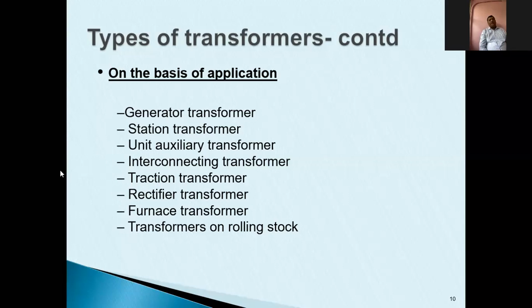When we are using rectifier transformers, in the case of HVDC substations, you will find the transformers are rectifier transformers. When you are coupling these transformers with rectifiers, there will be lots of harmonics. There will be lots of heat generated in this transformer due to harmonics. So we have to keep all these points into account. These harmonics, the higher frequencies, will affect my magnetic circuit. The eddy current losses will be more, the stray losses will be more. So I have to compensate for those.